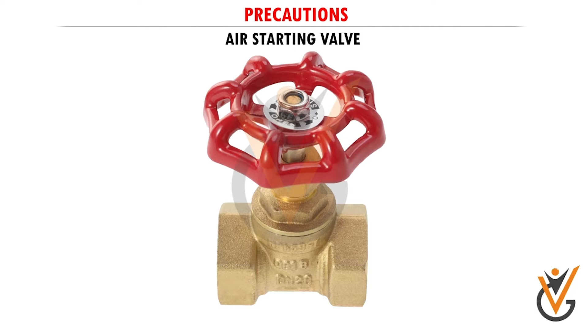Before starting work on the drive of any machine, for example the air starting valve for generators, it should be isolated to prevent the machine from being accidentally started. If the machine is operated remotely or on auto, put the switch to local.